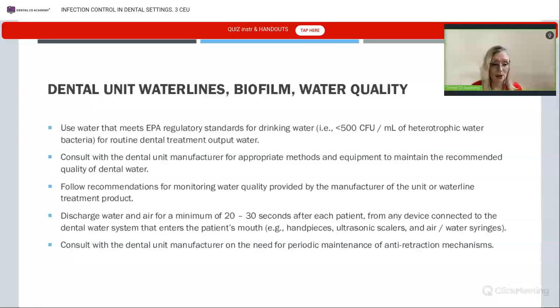All right. In terms of your anti-retraction mechanisms for your water lines as well as your vacuum lines, which are different, check with your manufacturer. So depending on what your system is, what your unit is, instructions for use. Is it going to be the straw method, etc.? Check with your manufacturer. And then test your water lines. We go into much more detail during the course that I present, which is available to you today on demand as well.